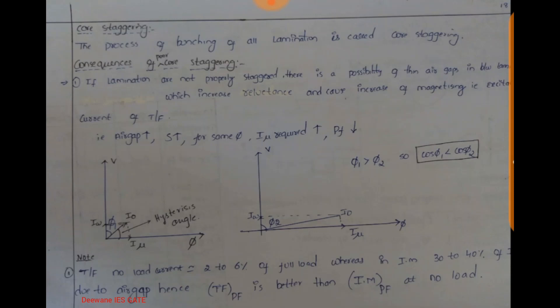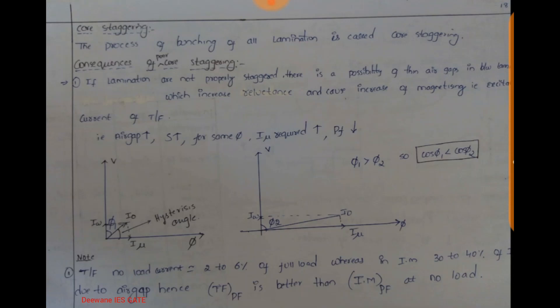Core staggering means the process of bunching all laminations. Suppose while bunching all laminations some air gap is present between laminations — what will it result in? The first disadvantage is that if an air gap is introduced between laminations, reluctance will increase, which causes an increase in magnetizing current. Air gap increases → reluctance increases → for the same flux, imu increases and power factor decreases.